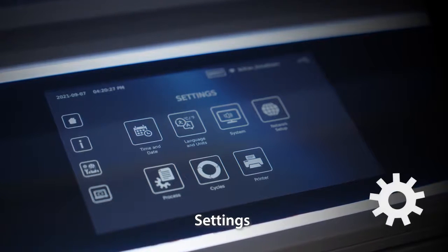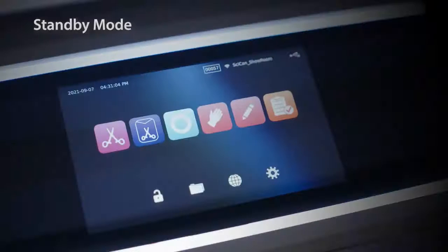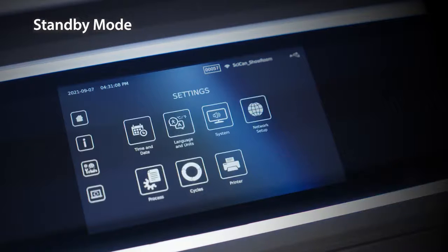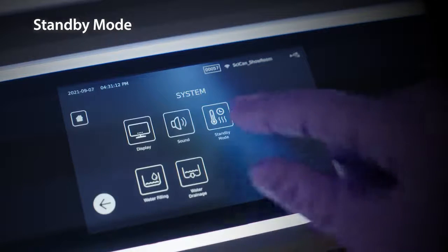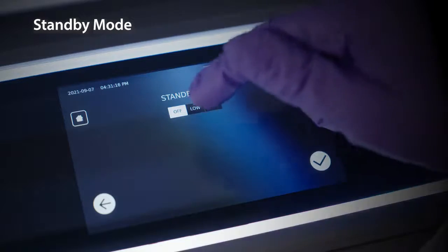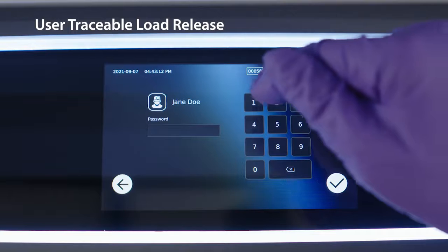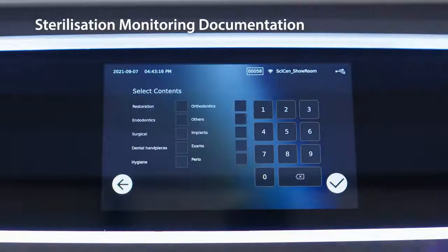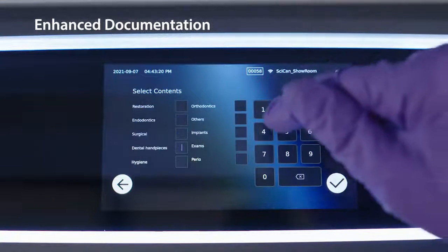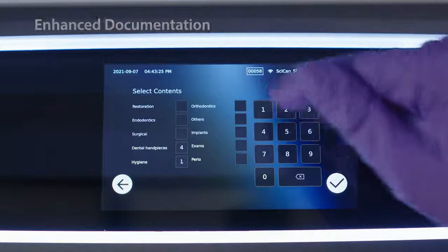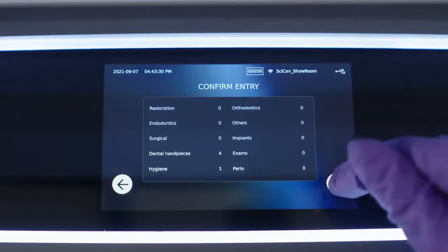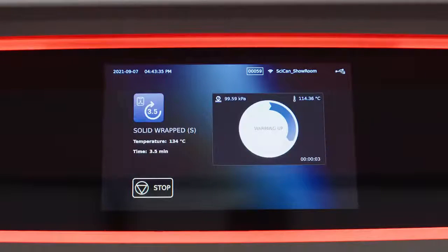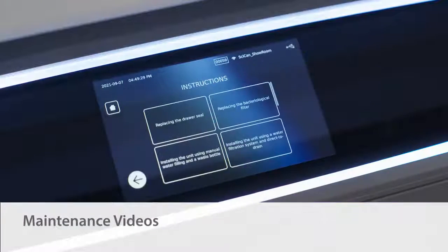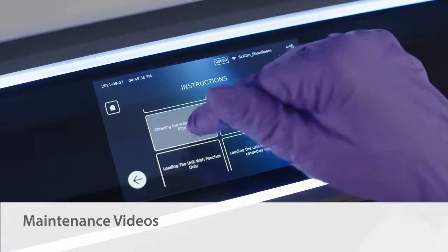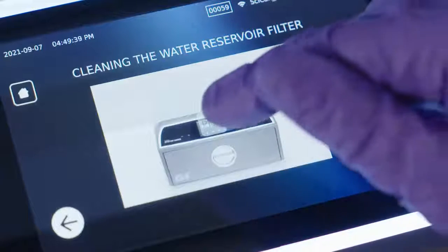The unit has several settings that can allow you to improve your workflow. Standby mode allows users to reduce time between cycles by keeping the chamber at a temperature that is optimal for your office's level of use. User traceable load release, sterilization monitoring documentation, and enhanced documentation features minimize the time required to manually document results. Maintenance videos and troubleshooting tips on the LCD screen put you in full control to keep your unit in good working order.